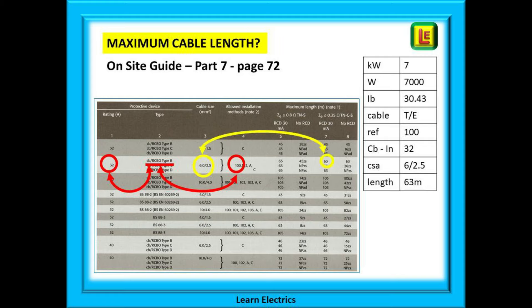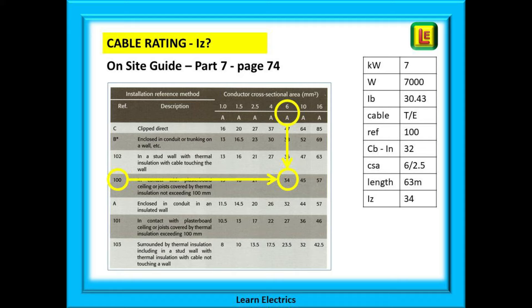This tells us that the cable should be 6 millimetres with a 2.5 millimetre earth, shown in a yellow circle on this page. Now assuming our earthing system is TN-CS — the second column from the right — this tells us the maximum length of cable run to avoid a voltage drop problem. In this case 63 metres, again circled in yellow. Finally we go to page 74 and check the maximum current rating or IZ for our 6 millimetre cable. With reference method 100 and a cable size of 6 millimetres the maximum current rating is 34 amps.